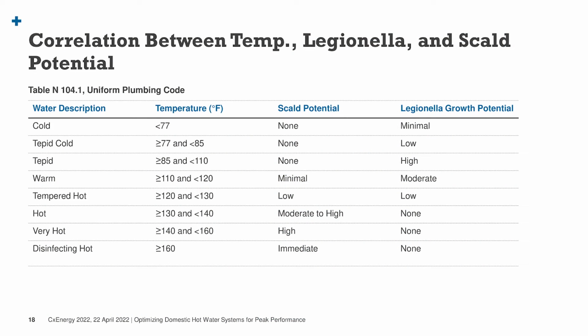The Uniform Plumbing Code, I think this last cycle, added this in the appendix, and it kind of addresses that topic of scalding risk versus Legionella risk. There are some things we've done to conserve energy, like lowering water heater set temperatures, to reduce the risk of scalding, but these can have the unintended consequence of creating an environment for Legionella growth.